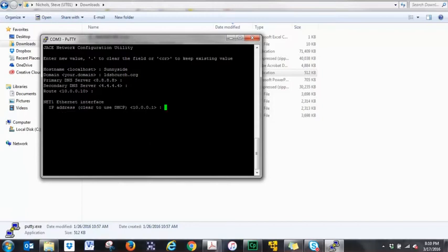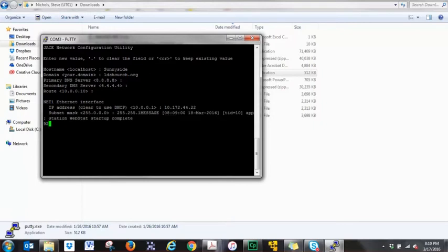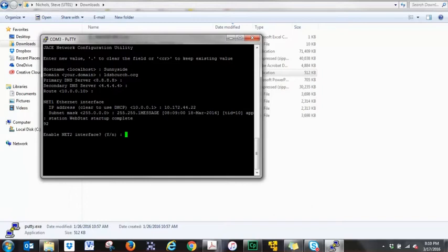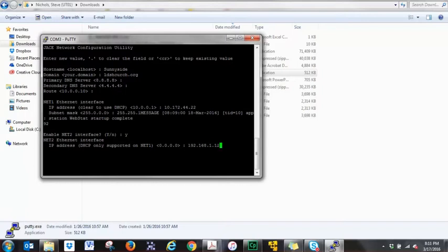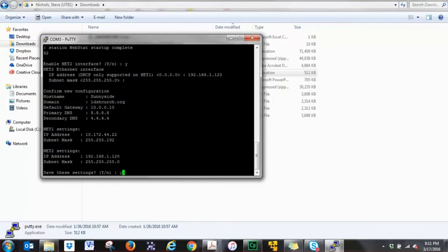Once you've got your router entered, you can enter in the IP address that you want to give your Webstat or your controller. So for this building, let's just say it is 10.172.44.22. And we'll say the subnet is 255.255.255.192. And we do want to enable port 2. This just explains that the Webstat startup is complete. It's not a big deal. We'll come back and make sure that our information was entered correctly. But if you want to activate port 2 on a Webstat, type in Y. This is the only place you can do it. And I always make it a habit of adding an address to port 2 on my Webstats, Web Security, and JACEs. This is kind of a back door. It's a way to plug into the unit by walking up directly and plugging into it. I always make mine 192.168.1.120. The subnet of 255.255.255.0. You want to save your changes? Yes.